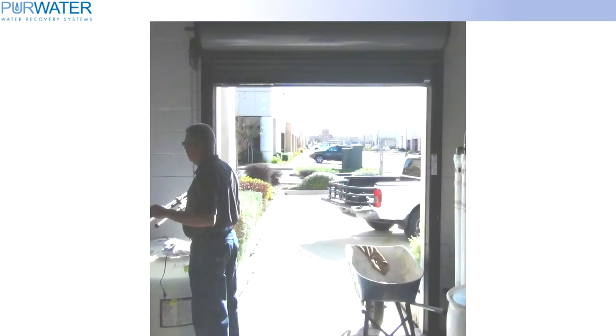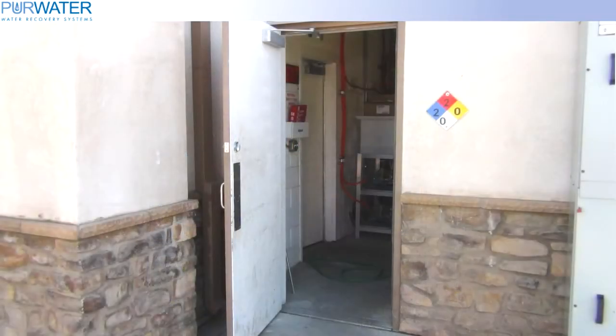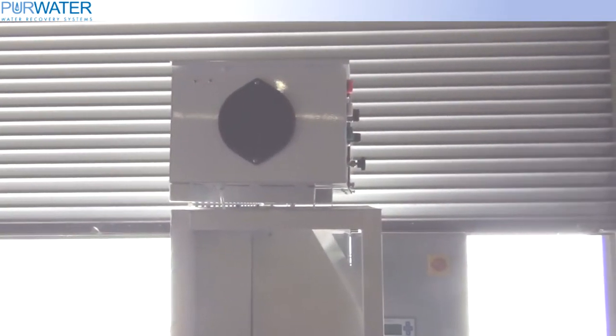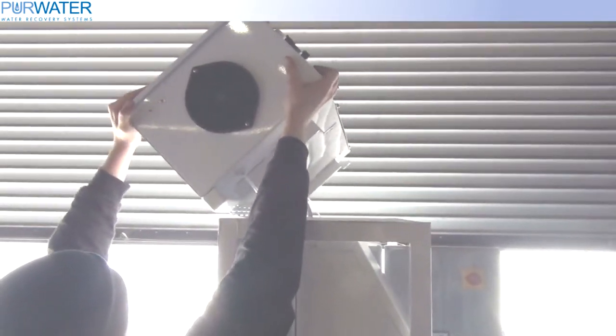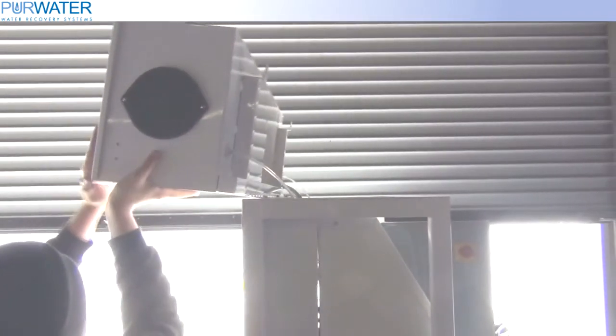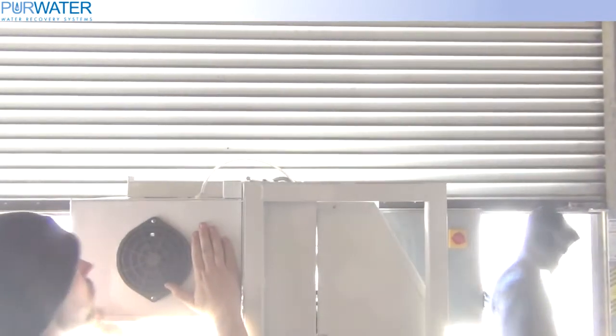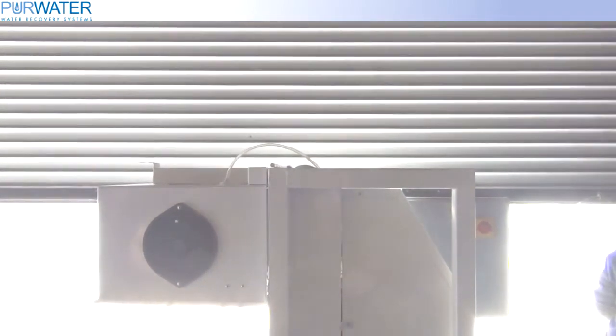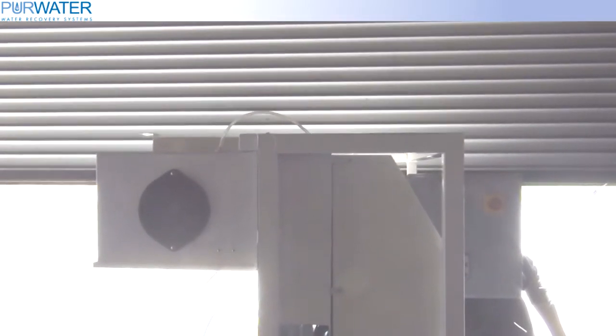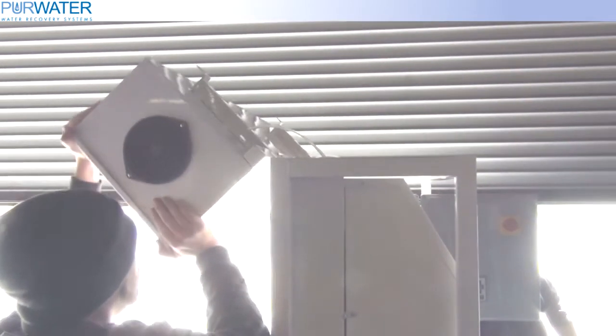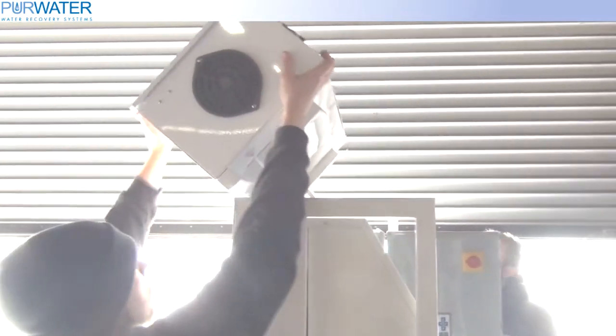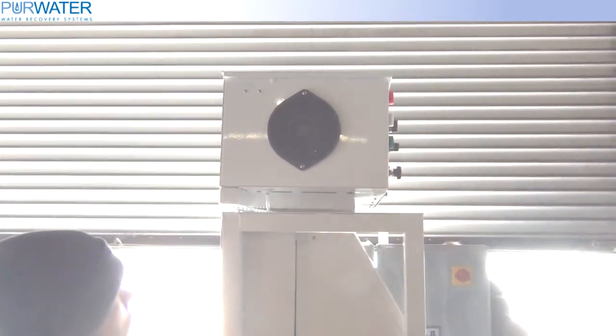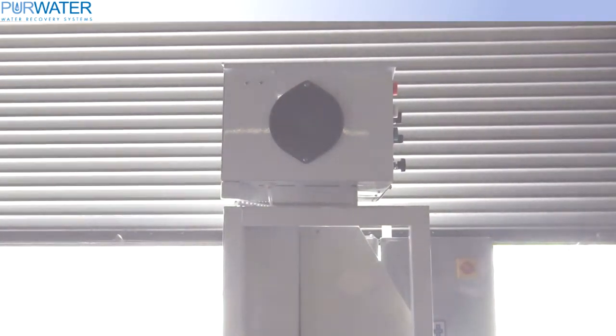For those of you who do not have a large bay door in the equipment room and have a standard door, the reclaimed system's ozone cabinet can be flipped down so you can easily push the reclaimed system through the door without having to tip the equipment. After removing two bolts, the ozone cabinet can be flipped via its hinge. Once you get the equipment into the room, you can flip the ozone back over and replace the two bolts. Be sure to be gentle while flipping the cabinet. The ozone cells within the cabinet are fragile.